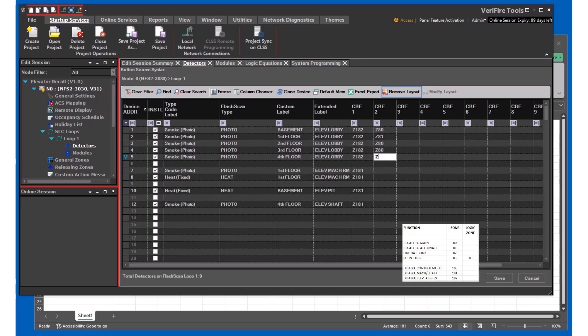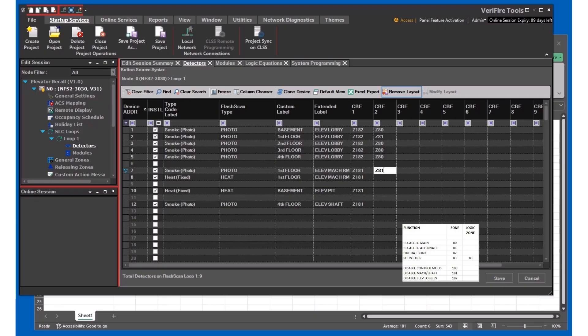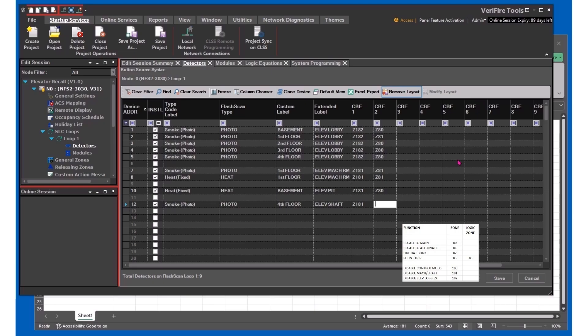All those floors are getting main recall. The machine room is going to get alternate recall to send it to the alternate landing. The pit will get main recall, and so will the smoke hatch or the top of the shaft.